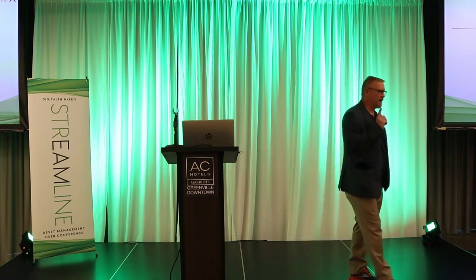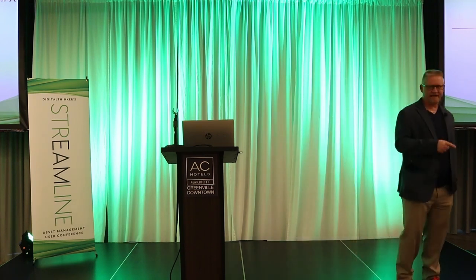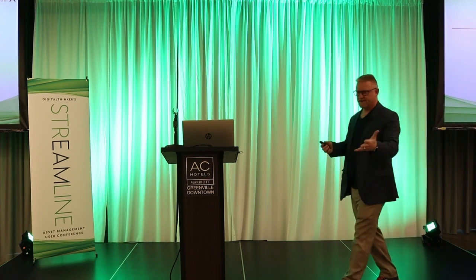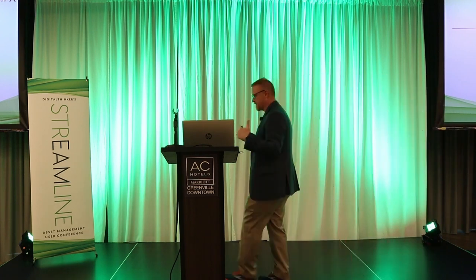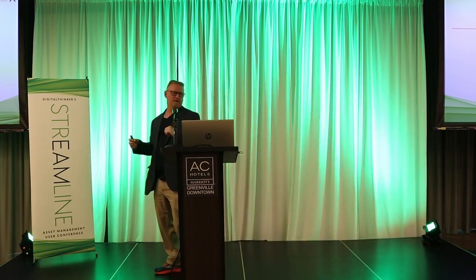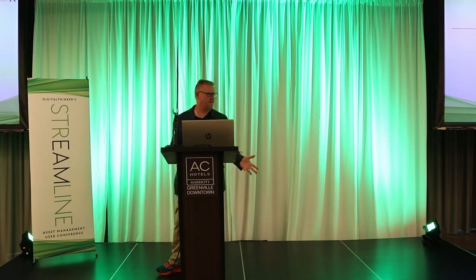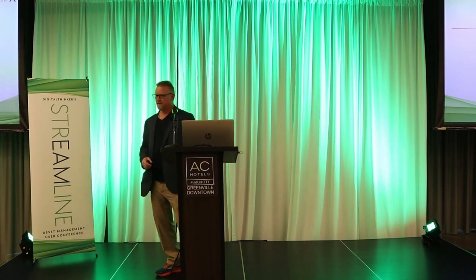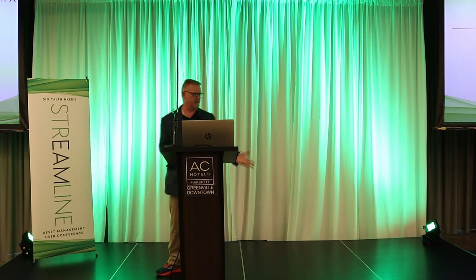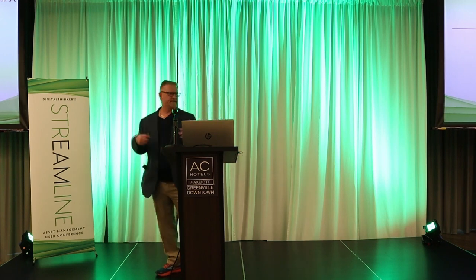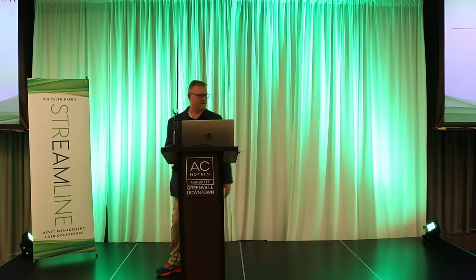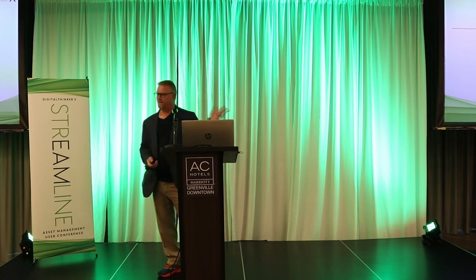Another interesting story. We have an underground water leak that we don't know where it is. I get a phone call that says, hey, George, I need you to check something out. There's a boiler feed pump problem or boiler water makeup problem because it's going through the roof. Well, what do you mean your boiler makeup water's going through the roof? Well, we don't know. We're not getting the same amount of condensate back. I got to figure out where the leak is. This is a 400-acre campus with 35 buildings fed from one central utility plant. How do you find the leak?